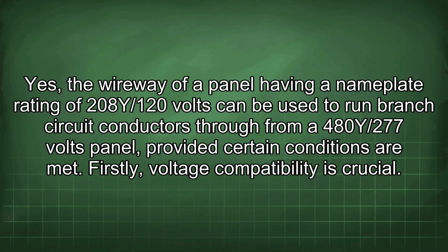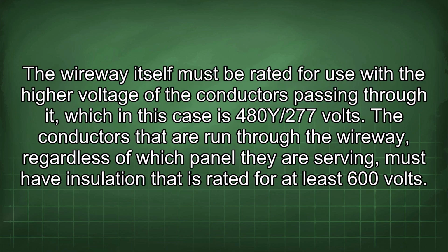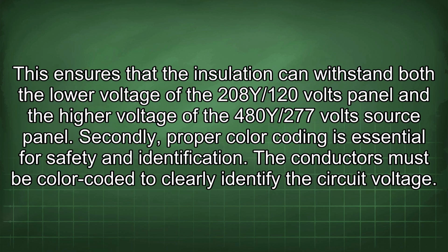Firstly, voltage compatibility is crucial. The wireway itself must be rated for use with the higher voltage of the conductors passing through it, which in this case is 480Y/277 volts. The conductors that are run through the wireway, regardless of which panel they are serving, must have insulation that is rated for at least 600 volts.